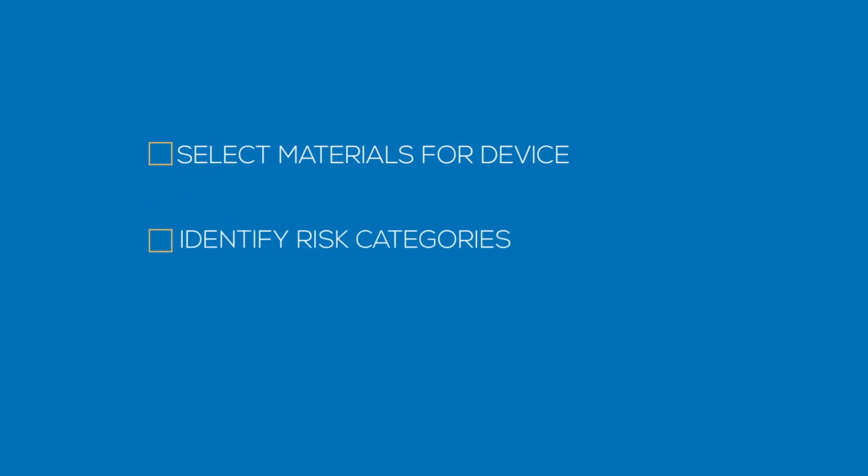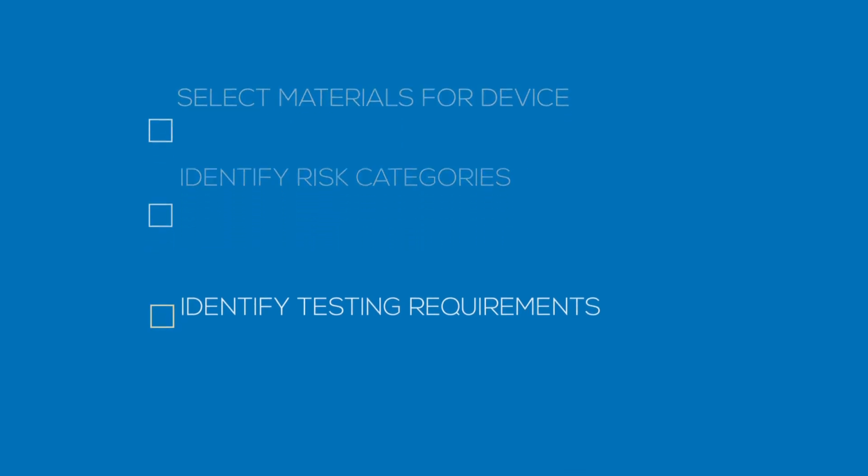Identify the nature and the duration of body contact with the device materials. And identify the testing requirements which will enable future clinical use. Where feasible, it is always better to use the same materials in your design prototype as will be used in the final product.